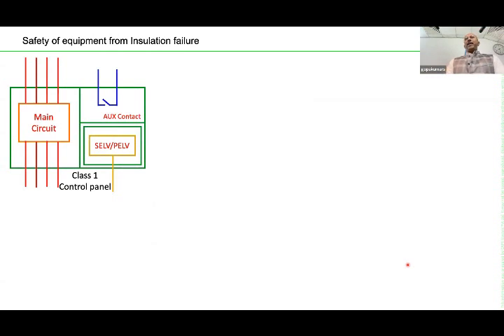Similarly, for example, an industrial application, let's say a control panel, which has an operating voltage, let's say some portion operating at 230, 400 volt, some portion operating at 24 volt, some portion operating with a different communication device. Under these conditions, some basic insulation is required between different devices. So the panel builder should have made those arrangements properly.